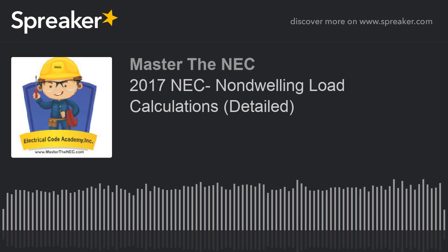So the next thing you look at is 220.44. Now 220.44 tells me that I can take the first 10,000 VA of these receptacle loads at 100%, and then the remaining portion over that at 50%. And it doesn't give a plateau on this. It just tells you flat out that I can take the first 10,000 at 100% and everything after that at 50%.